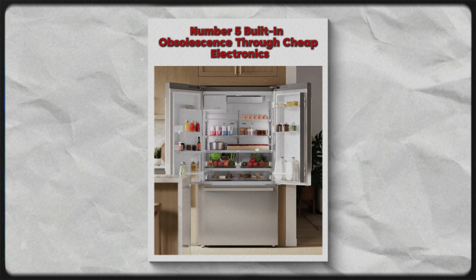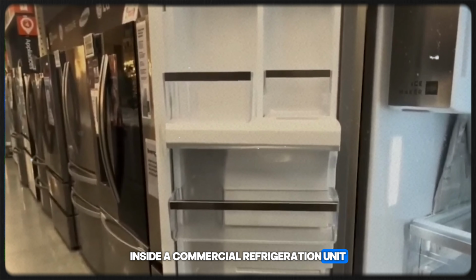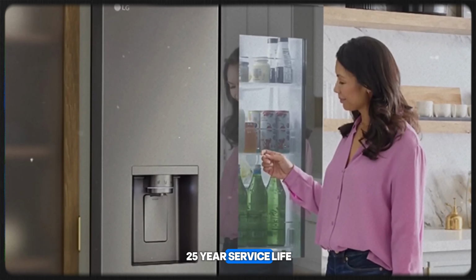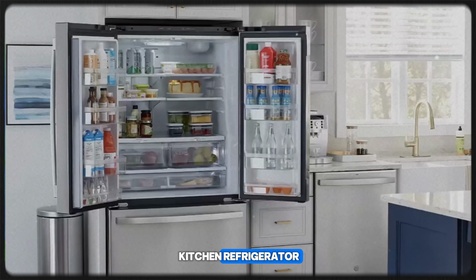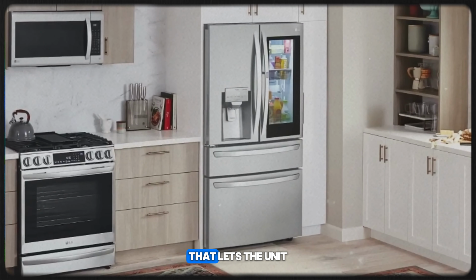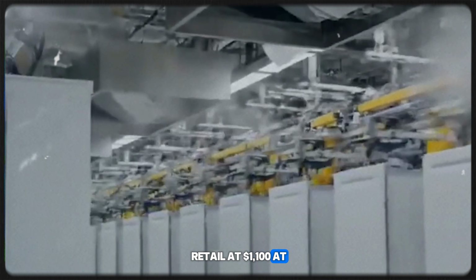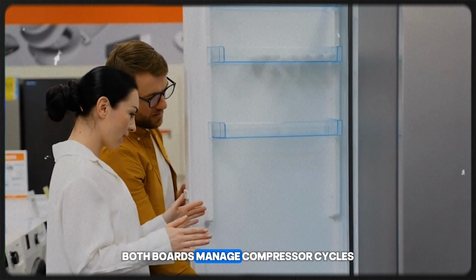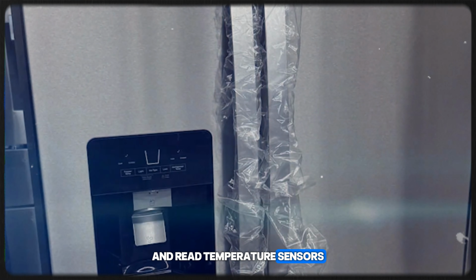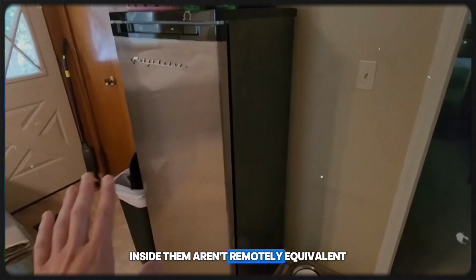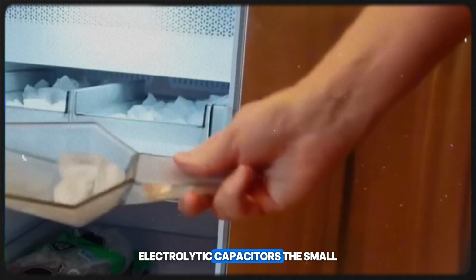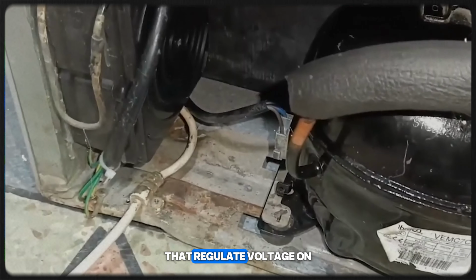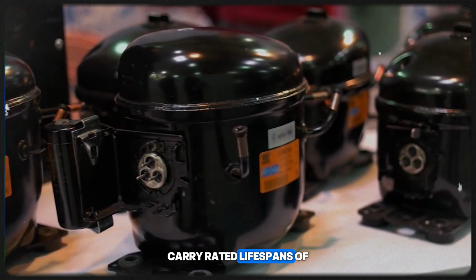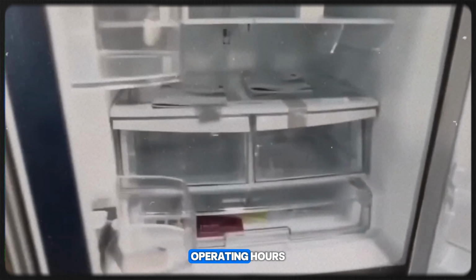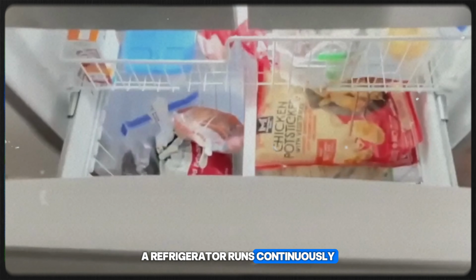Number 5. Built-in obsolescence through cheap electronics. The control board inside a commercial refrigeration unit gets specified for a 25-year service life. The one inside your kitchen refrigerator gets specified for a price point that lets the unit retail at $1,100 at a big box store. Both boards manage compressor cycles and read temperature sensors, but the components inside them aren't remotely equivalent. Electrolytic capacitors, the small cylindrical components that regulate voltage on the board, carry rated lifespans of 2,000 to 5,000 operating hours. A refrigerator runs continuously.